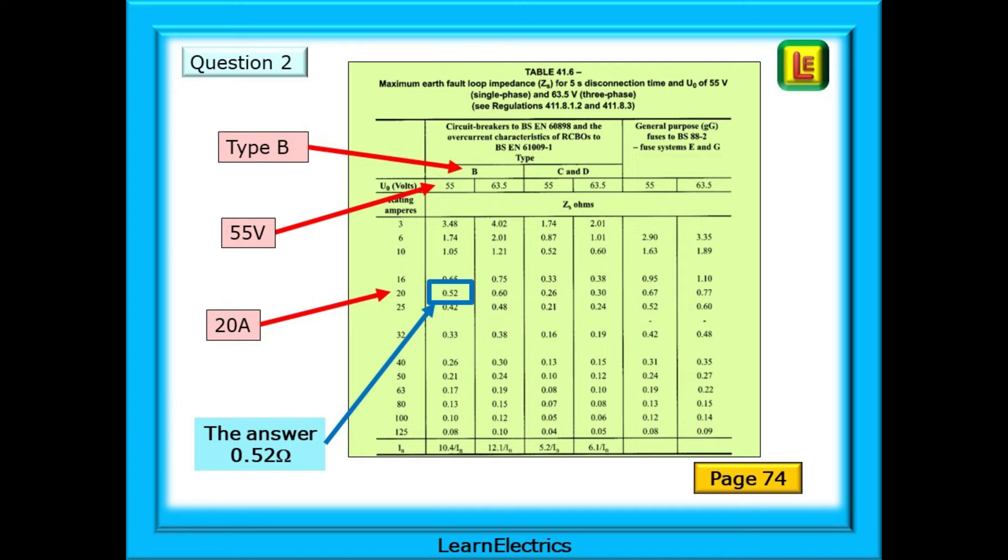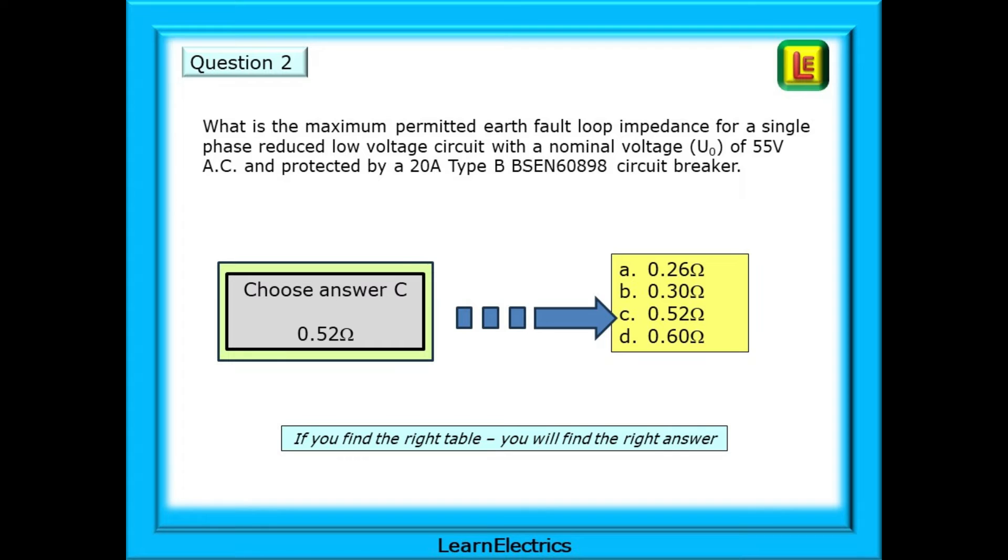Table 41.6 looks complicated. It's not. Follow the question. A type B breaker, so we have a choice of just two columns. 55 volts, so now we're limited to one column. 20 amps tells us which row we need, and where the row and column cross is the answer that we need, 0.52 ohms. We should choose answer C. The maximum earth fault loop impedance permitted is 0.52 ohms. If you find the right table, you will find the right answer.